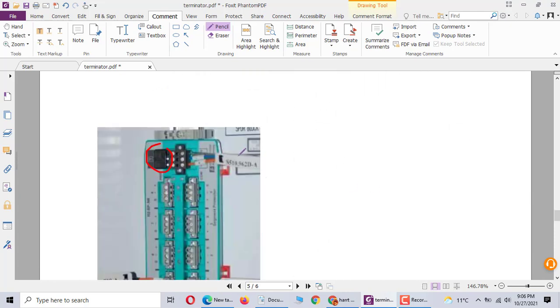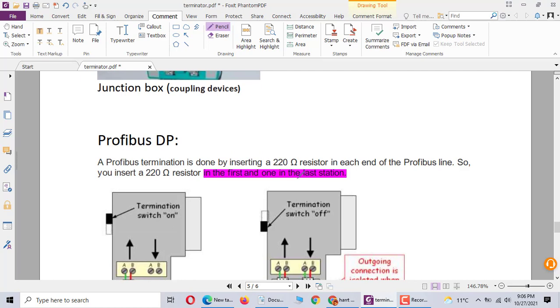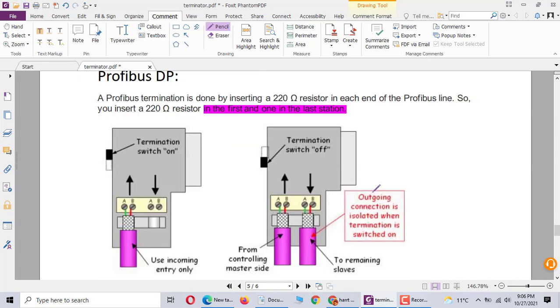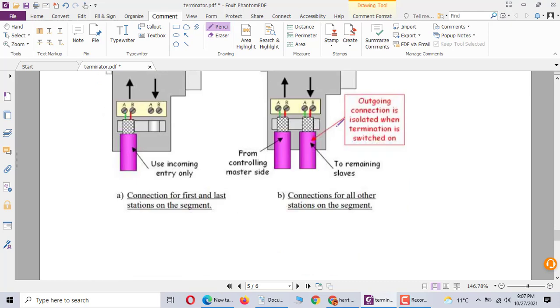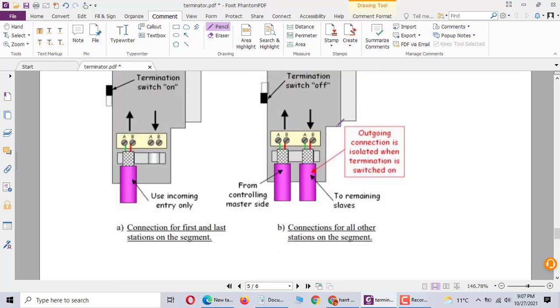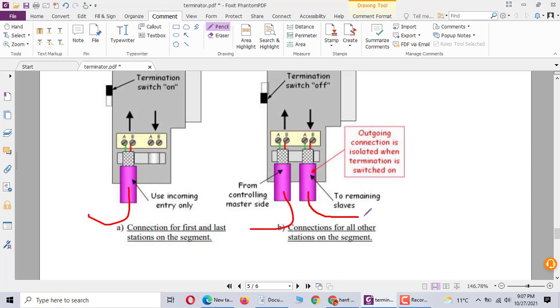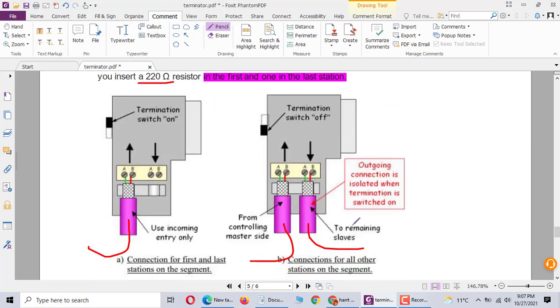Profibus DP is the same thing. The first one and the last one use 220 ohm resistor. In the first junction box and the last junction box you have the termination switch, you use on. In the middle you use switch off. From here to here, for this one should be termination switch off.